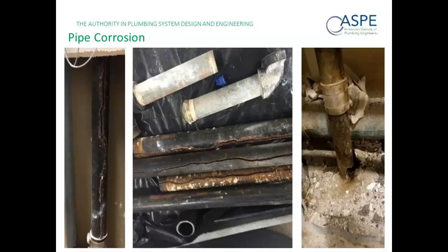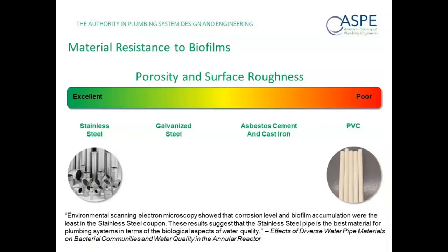And I think conceptually, a lot of people think in plumbing that, all right, I replaced it with PVC or a resin-based trench liner, and in actuality, they've done something to incorporate a system that's more porous than what they had before. Clearly, cast iron is porous in many cases, but the gold standard is stainless steel.